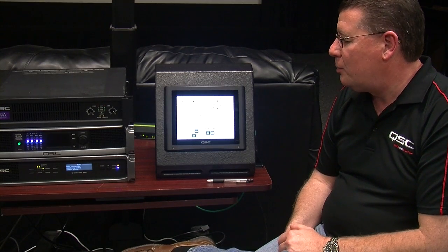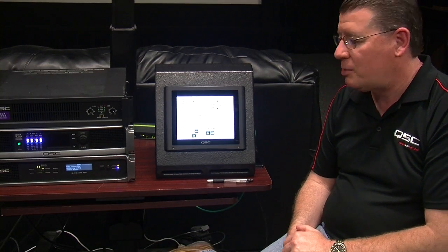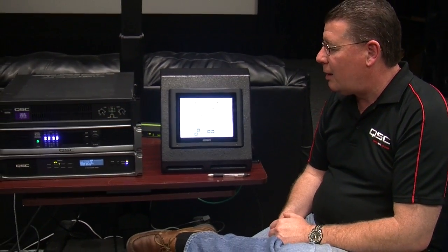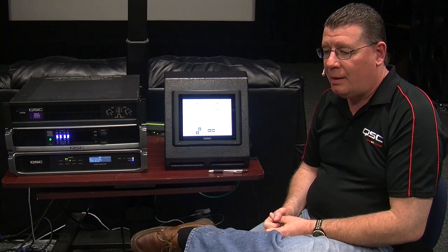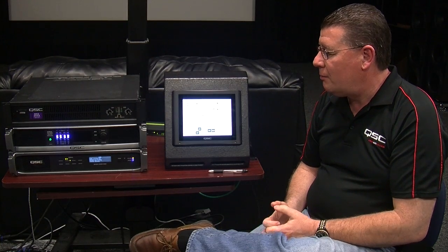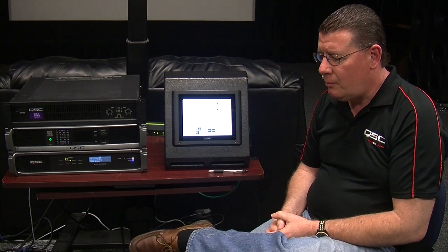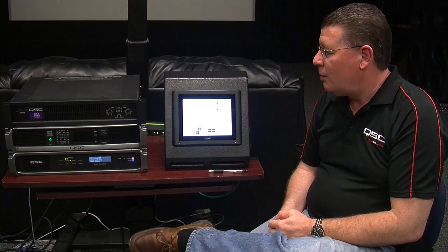This is why we have to be careful when we're speccing our AC current draw specifications, that worst case, we use a 1/8 figure when we're calculating the requirements for circuit breakers. That 1/8 value is on the QSC data sheets and website, and it really is a good real-world number to use when calculating how big of a circuit breaker you need to provide.